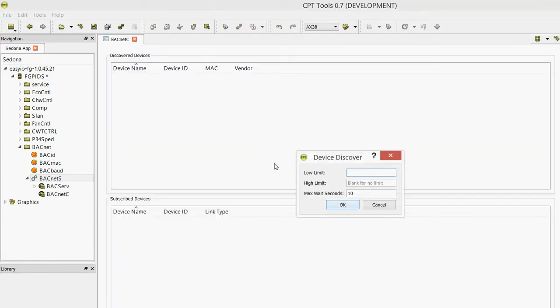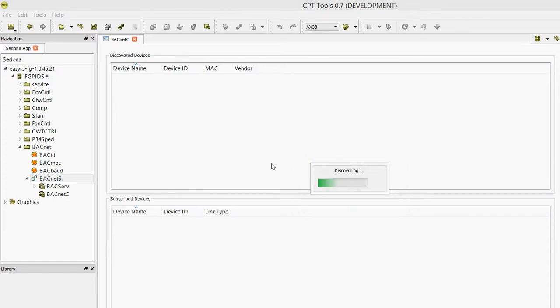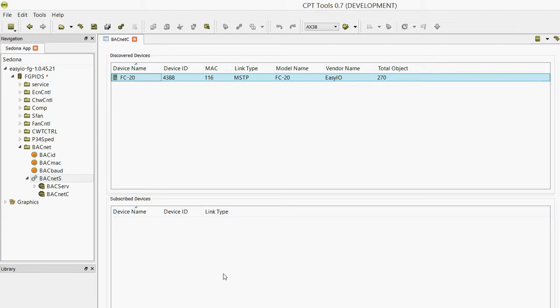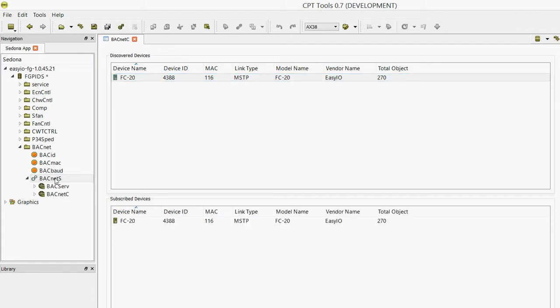Now use the discovery button to discover the devices on the network. If you've got quite a few devices, it's better to increase this maximum wait time so it doesn't time out. We're discovering now. That discovery has finished and we have ourselves an FC 20 here, MAC address 116, device ID 4388. Just remember that device ID. If we now subscribe to that, you will see the controller was just created here.